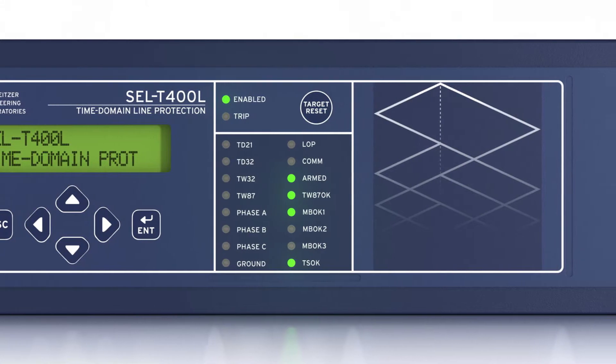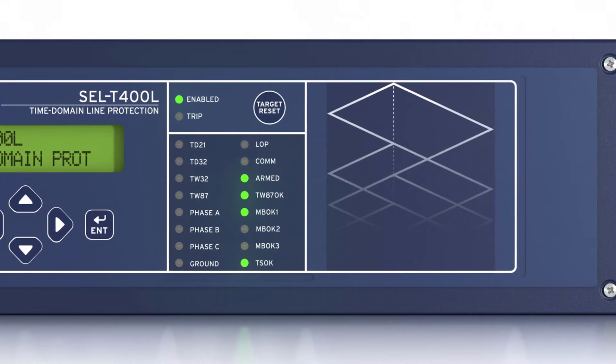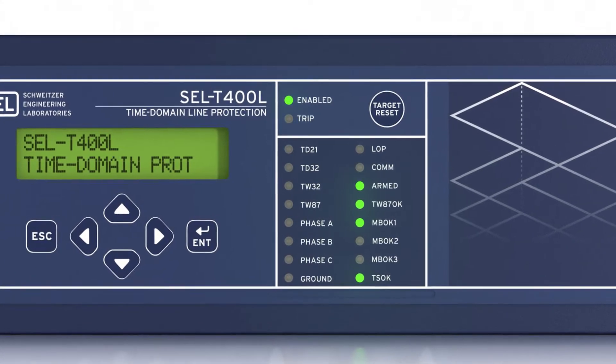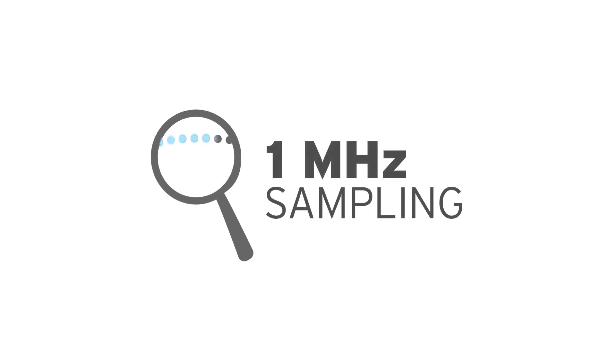By moving towards time-domain and traveling wave principles, we're acting on the samples. And this relay will sample at one megahertz. It means that once every microsecond, we're taking a measurement on the power system, using that information to make a tripping decision. It's never been done before.